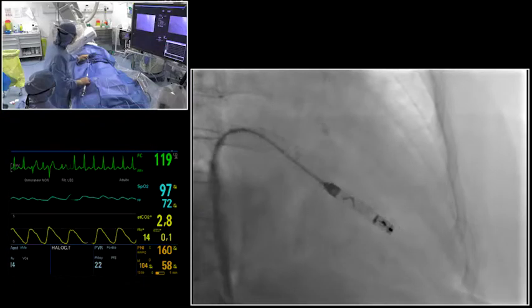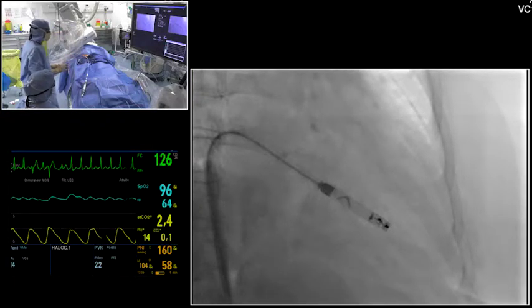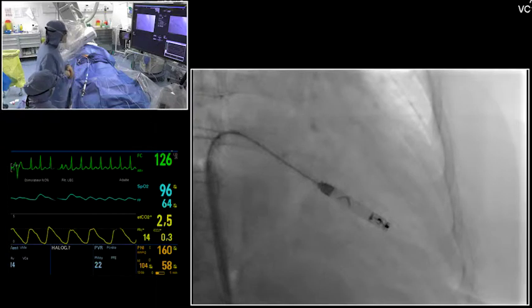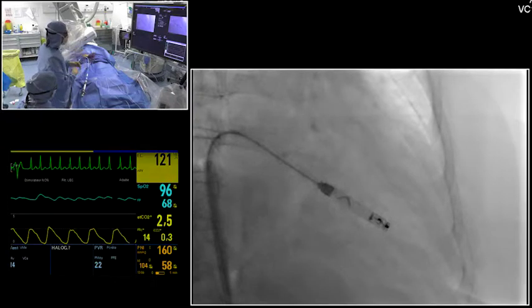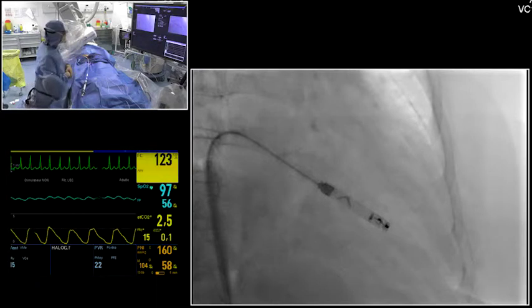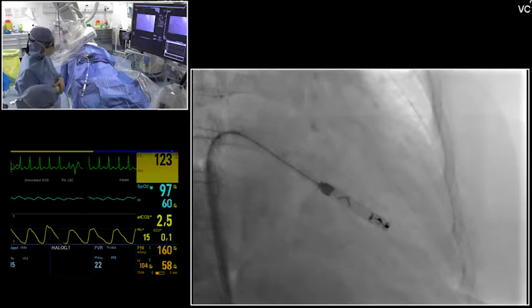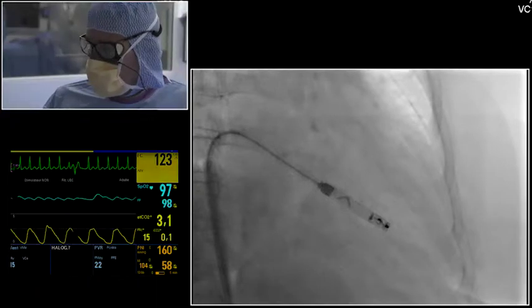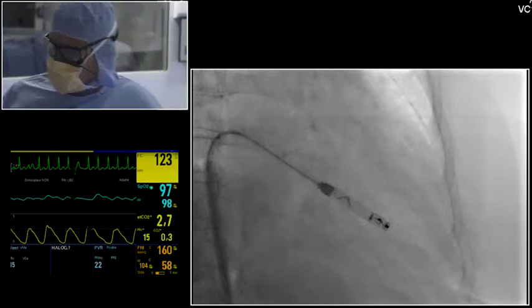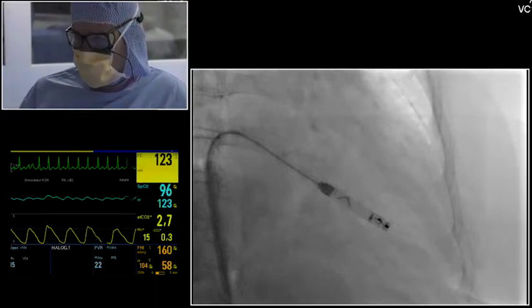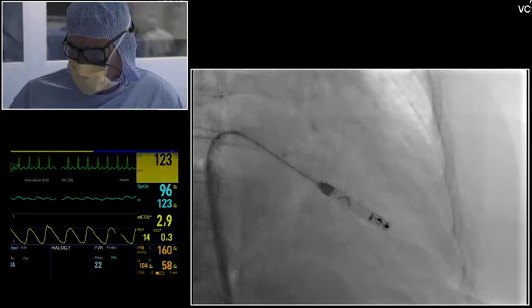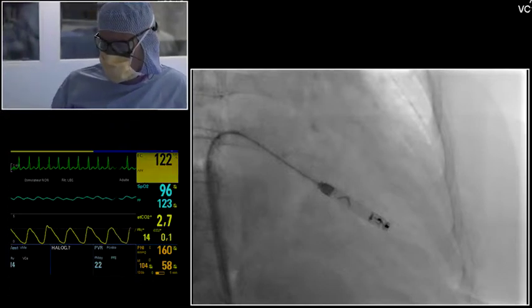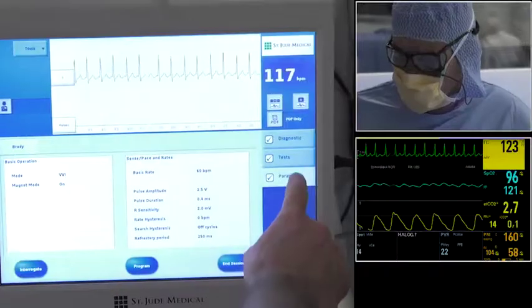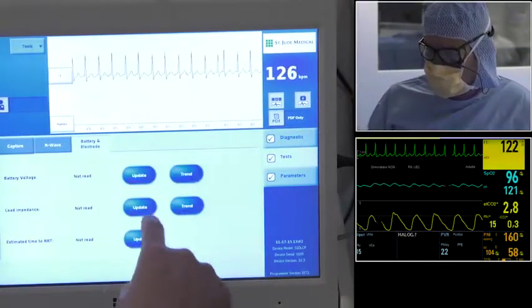The position seems very good. My advice is to not push the nanostim on the wall. I think we can see the movement of the right ventricle, and the curve seems very good, very harmonious. The next step will be to check the measurements before screwing, to check the detection, to check the impedance and the threshold. So I will start with the impedance.